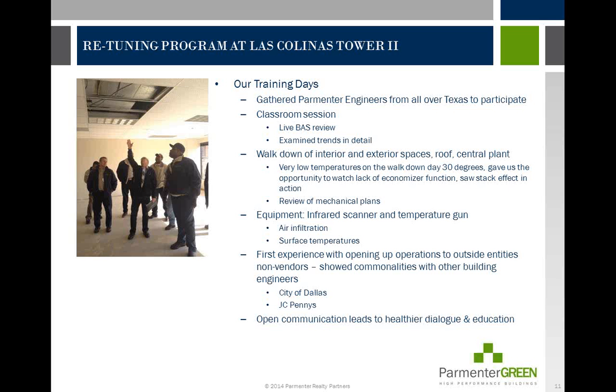It gave us an opportunity while walking the building to see where cold air was coming in and heat was leaking out. We also noticed the economizer function wasn't working, and the engineers on the property were a little reluctant to use the economizer even if it was working. They felt like they couldn't cool the building in the wintertime without using the chillers.